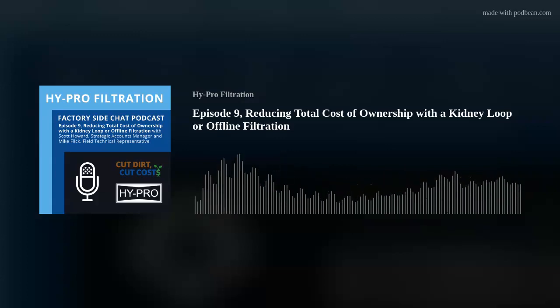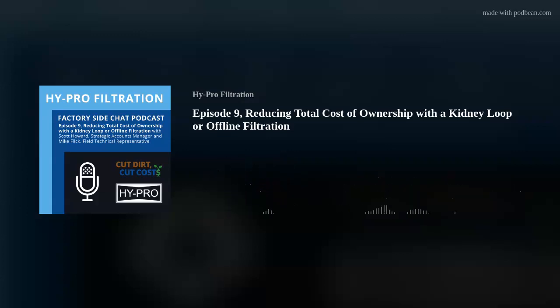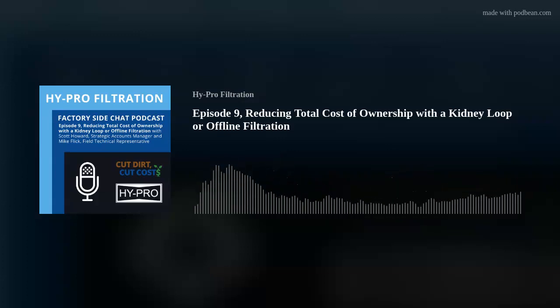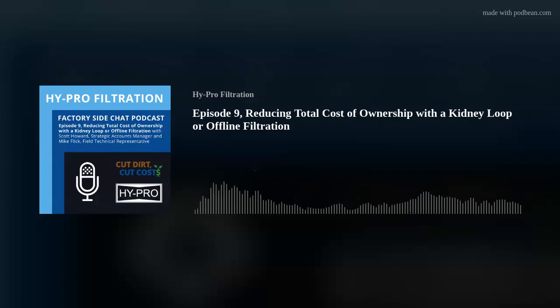It's a clean application. We assume that the oil is going to be pre-cleaned before it's even connected, but going through the filter one more time just helps ensure that we are adding oil that's cleaner than the system and not dirtier than the system, so that we're not adding to any problems that may arise. And then also an accurate sample port location for sample acquisition so that we can have data on the lab report that's actionable and trendable. It's believable. And so those are some other benefits of having a kidney loop added to the system. But on the total cost of ownership side, if we recommend a kidney loop, it is definitely going to benefit the total cost of ownership for that customer on an annual basis.